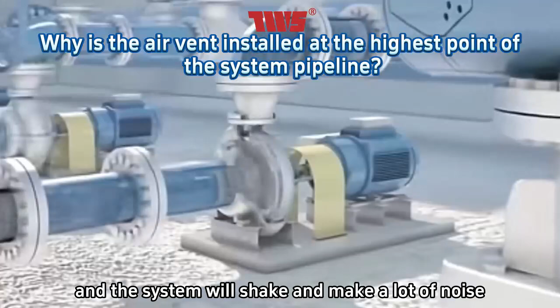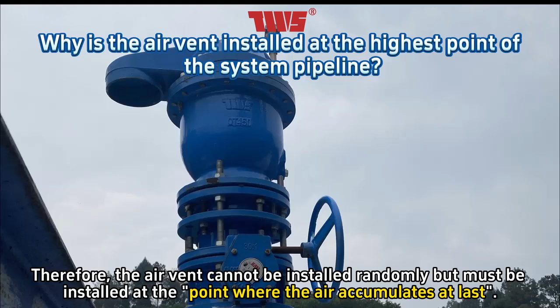The pump will suck in air and cause water hammer, and the system will shake and make a lot of noise. Therefore, the air vent cannot be installed randomly but must be installed at the point where the air accumulates at last.